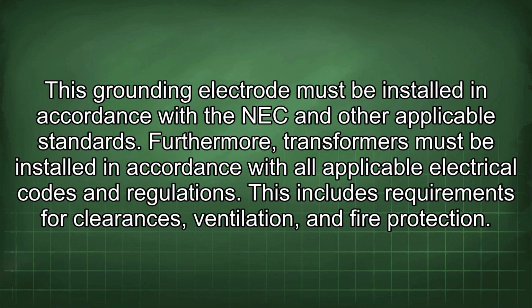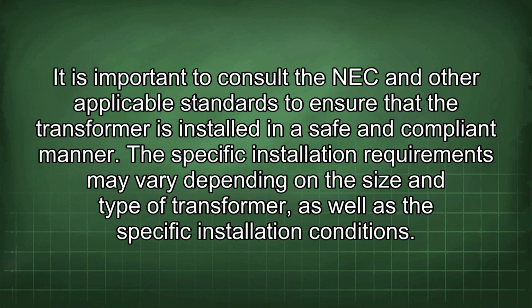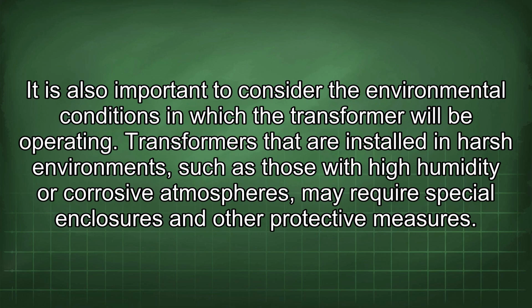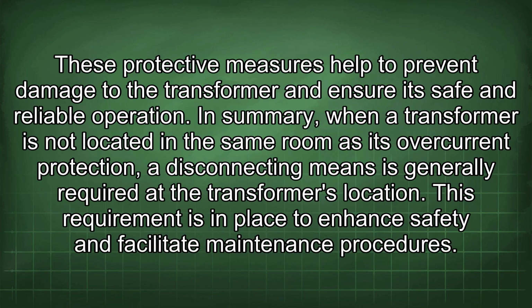Furthermore, transformers must be installed in accordance with all applicable electrical codes and regulations. This includes requirements for clearances, ventilation, and fire protection. It is important to consult the NEC and other applicable standards to ensure that the transformer is installed in a safe and compliant manner. The specific installation requirements may vary depending on the size and type of transformer, as well as the specific installation conditions. It is also important to consider the environmental conditions in which the transformer will be operating. Transformers that are installed in harsh environments, such as those with high humidity or corrosive atmospheres, may require special enclosures and other protective measures.